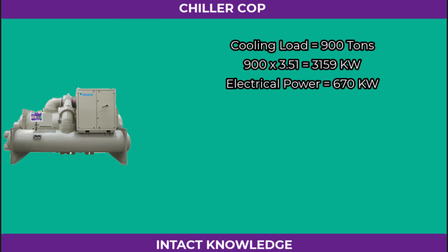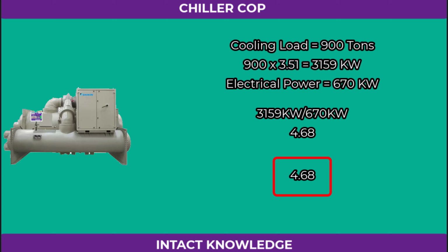Now, applying the formula, 3,159 kilowatts divided by 670 kilowatts, which gives us 4.68. That means the chiller's efficiency is 4.68. In simple words, for every 1 kilowatt of electrical energy, the chiller provides 4.68 kilowatts of cooling.